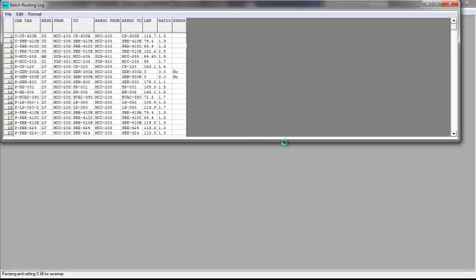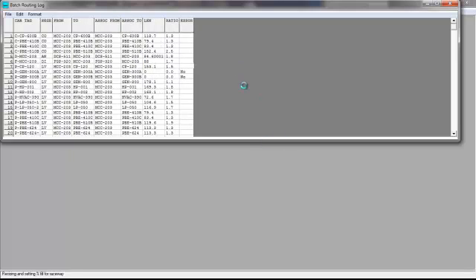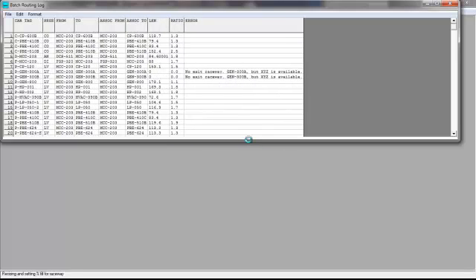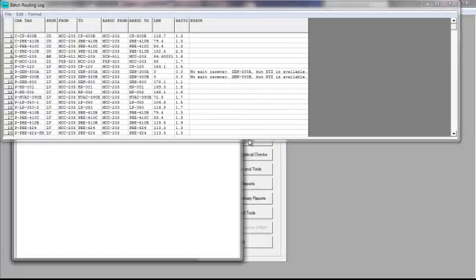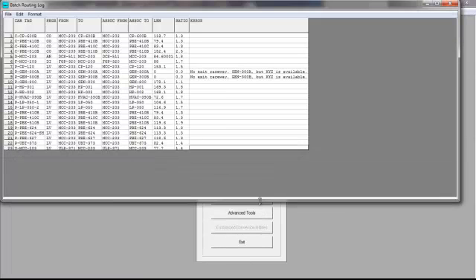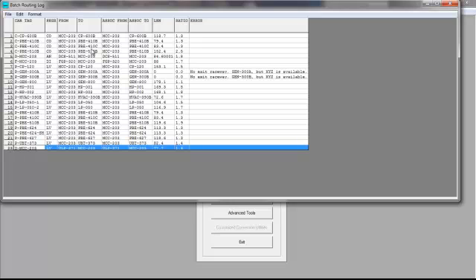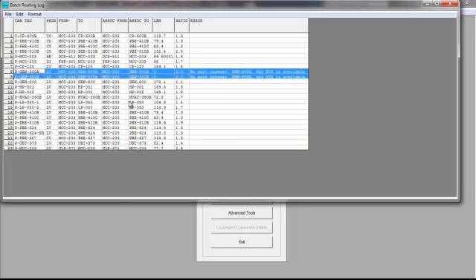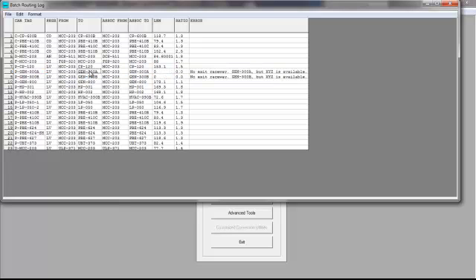I've got a larger list this time. If you notice it said that two of the cables failed. There are 23 cables in our list. Of those 23 I've got route lengths on 21, but these two didn't route and it's going to tell me why in the error message. It's going to say there is no exit raceway but there's an XYZ available. So that's for generator 300A and 300B.